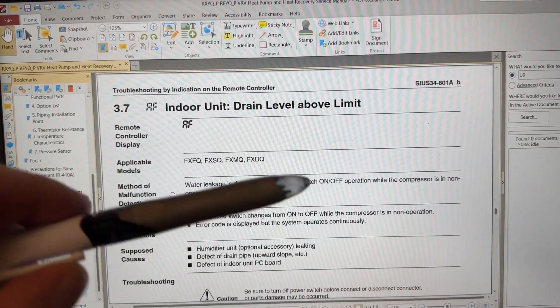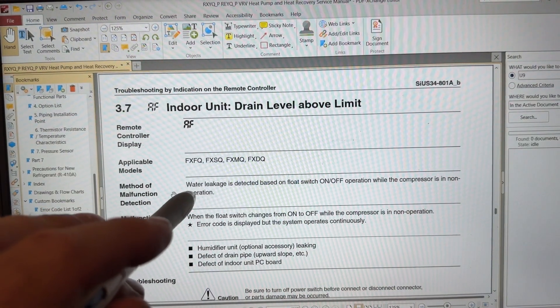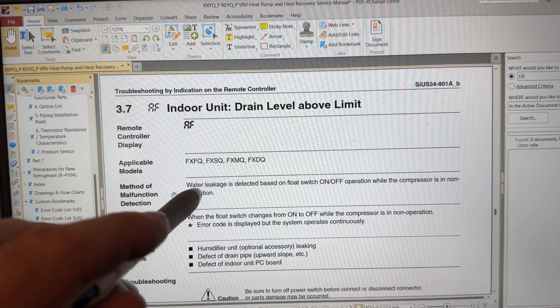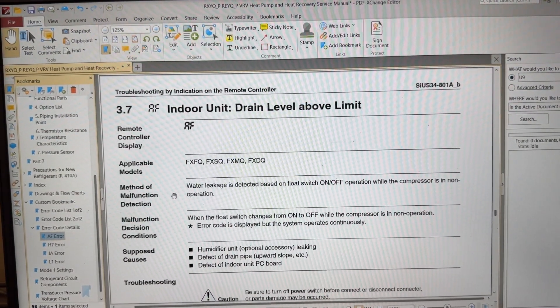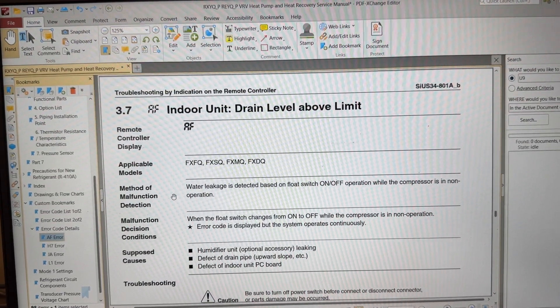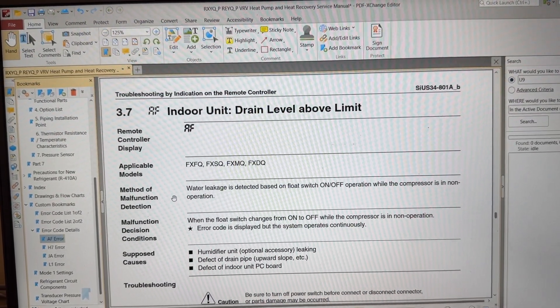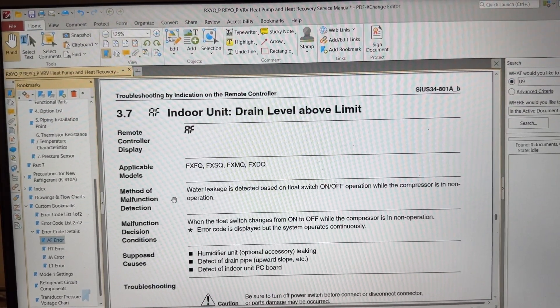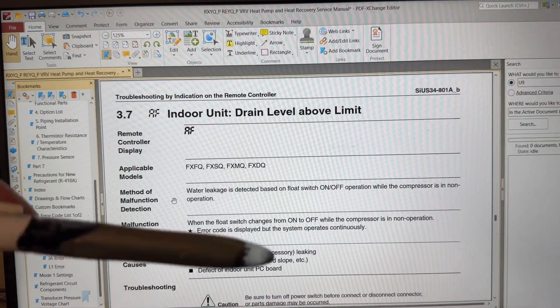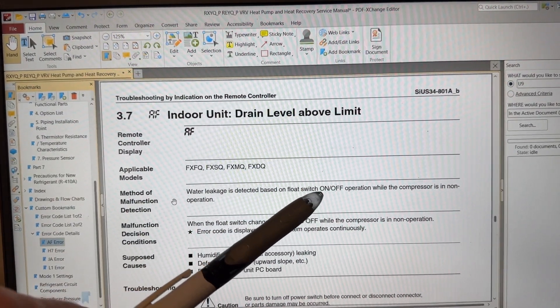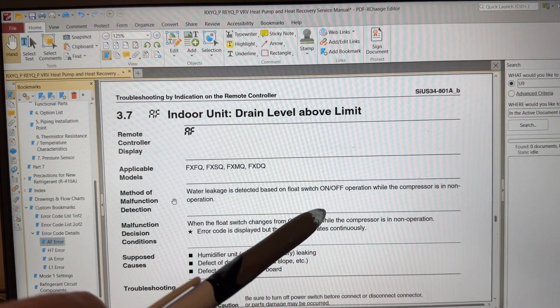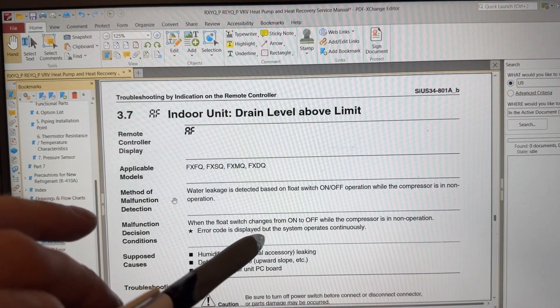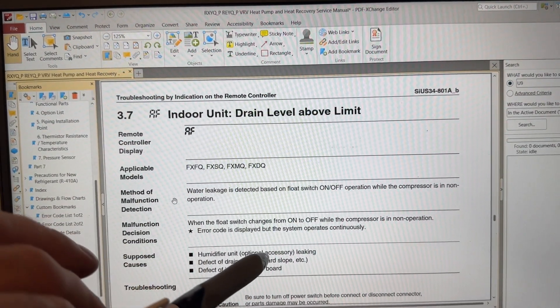Alright so the float switch in these units if I'm not mistaken and this is pretty typical of all VRF fan coils. When they're in cooling mode the drain pump is like a misting sling style so it's going to be running continuously and this float switch here is not to activate the pump. The pump runs continuously. The float switch is there to let the unit know if there's a problem and that water level has risen further than it should.